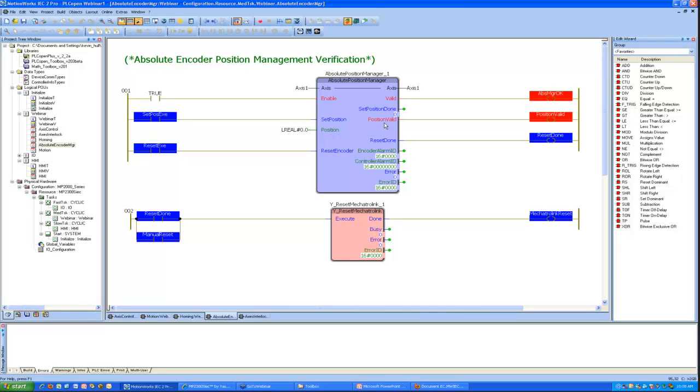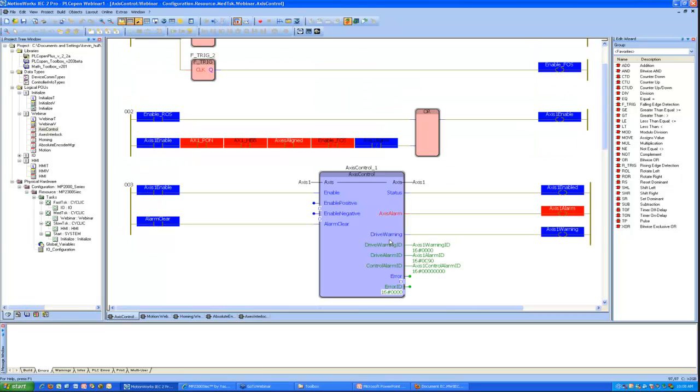So let's demonstrate that real quick. I can actually demonstrate an encoder alarm by disconnecting the encoder from the amplifier momentarily. Okay, so at this point we don't have an absolute encoder alarm yet, but I have unplugged the encoder and reconnected it. You'll see that if I switch over to the axis control function block, there is an axis alarm. And that alarm is AC9, which means encoder disconnection.